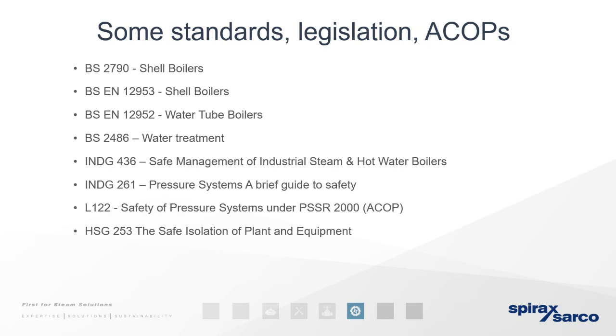INDG 436 for safe management of industrial steam and hot water boilers. So again, that's more of a standard legislation. L122, safety and pressure systems, so it's the pressure regulations. And HSG 253, which is the safe isolation of plant and equipment. So I'll leave that there just for a second longer, just in case you want to make note. There will be local legislation depending on what country you're in. When there is no legislation in place, which is rare, you can always fall back on these, because there are many boiler manufacturers around the world that, not all of them, but some of them, work to these standards.